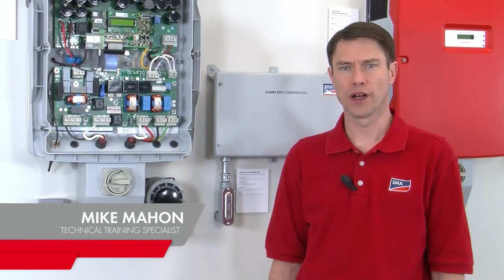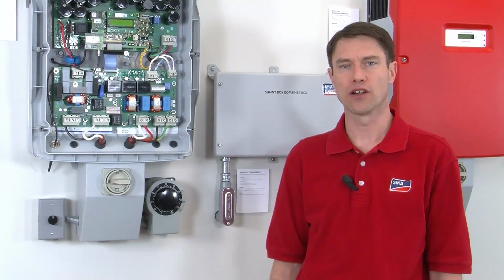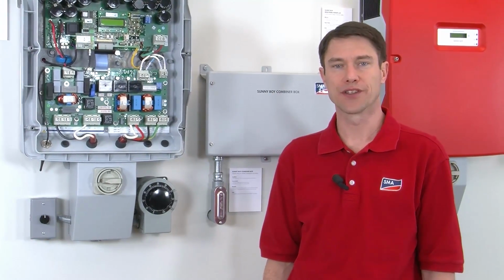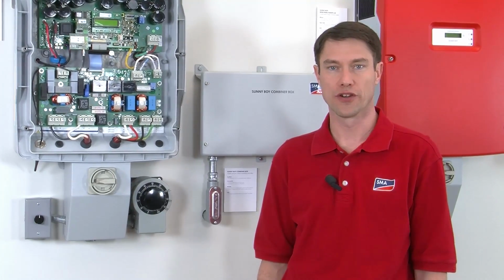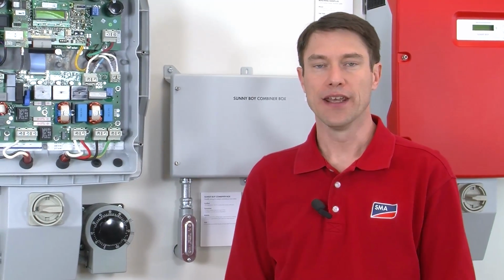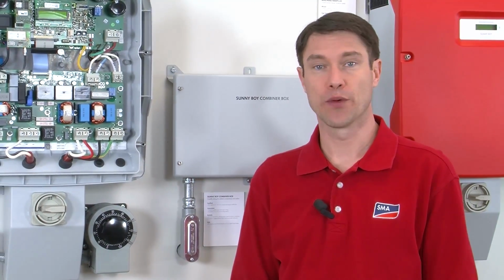In this tech tip, we're going to talk about common causes for error codes on the AC side of the Sunny Boy US series inverters. One of the most common error codes we see on the Sunny Boy US series relating to the AC side is FAC, and that means frequency on the AC side is out of spec.